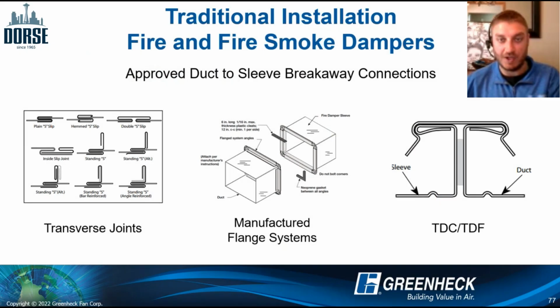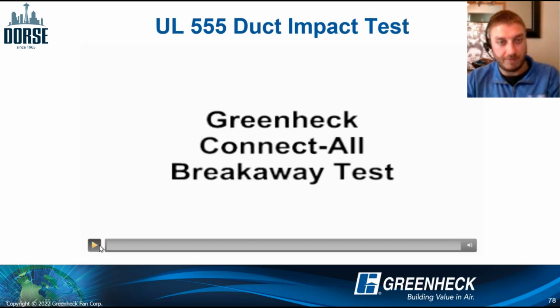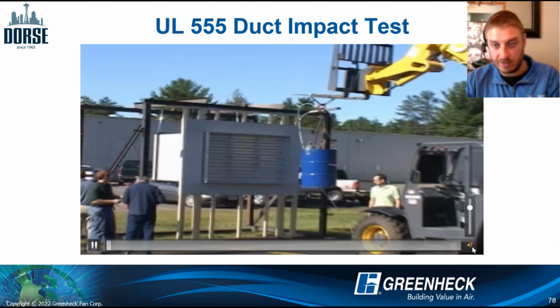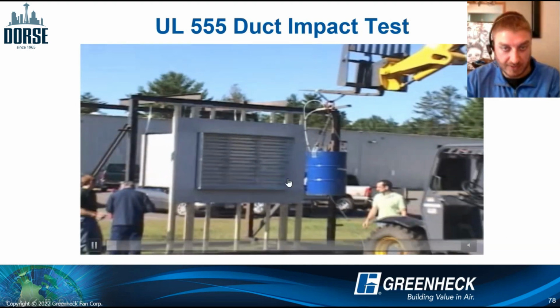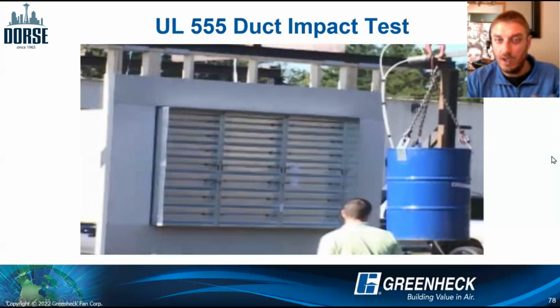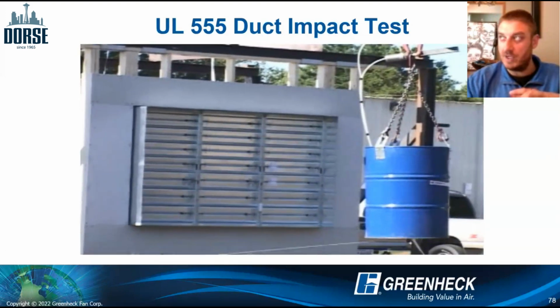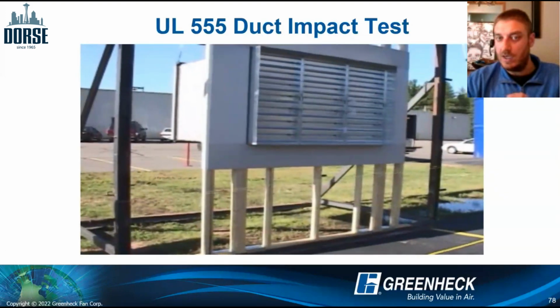And then if we are connecting ductwork to it, we need to use an approved breakaway connection. So I mentioned that the damper sleeve can only come so far out of the wall before we have to make a connection, and that's because we have to pass one of these tests. If I can get the video to play here. So this is a UL 555 Duct Impact Test.